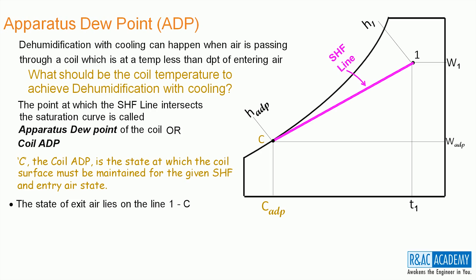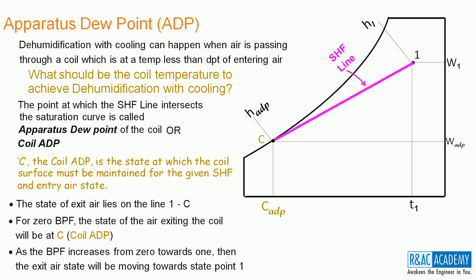During this process, the state of the exit air lies on the line joining 1 to C. For a zero-bypass factor, the state of the air exiting the coil will be at C, i.e. coil ADP. As the bypass factor increases from 0 towards 1, then the exit air state will be moving towards state point 1. For the bypass factor of x, the state of the air exiting the coil will be at 2 with its properties being T2, W2 and H2.